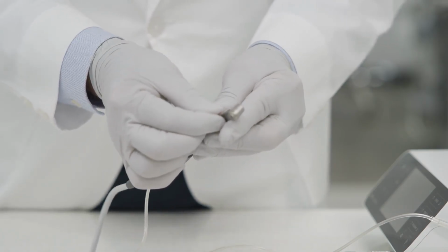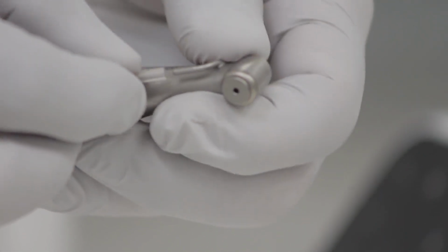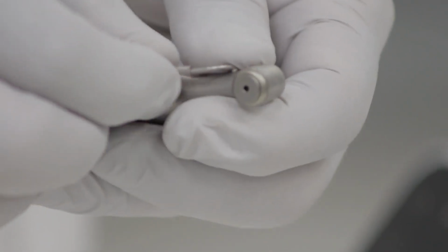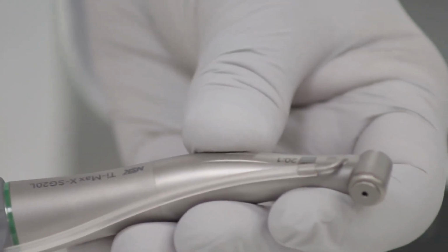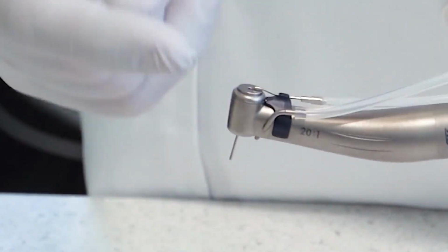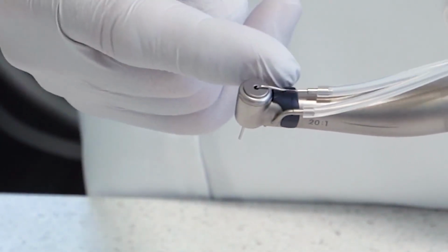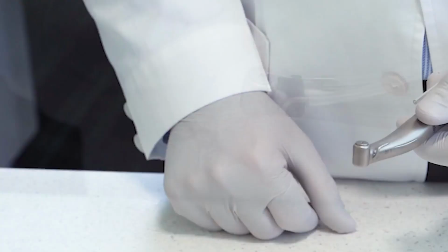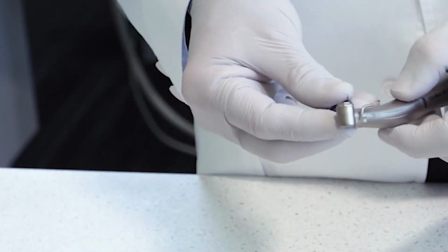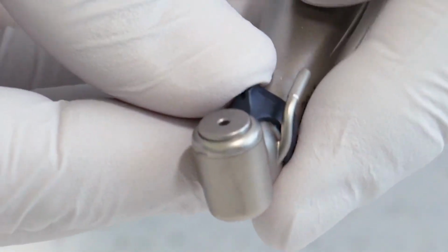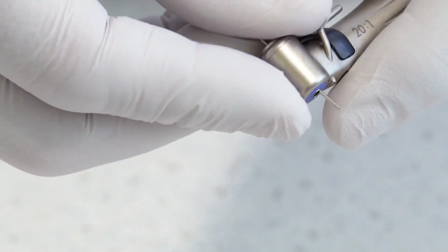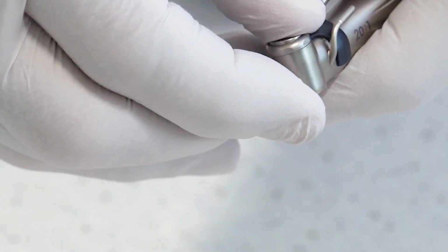There are 2 ways to connect the irrigation tube to the implant handpiece depending on the type of the drill being used in the operation. Single external spray is very common. In this case, connect the end of the irrigation tube directly to the external spray nozzle of the handpiece. For dual irrigation, use the internal spray nozzle in addition to the Y connector. The internal spray nozzle is mounted on the neck of the handpiece using the black holder. With a slight push, it will click into place.